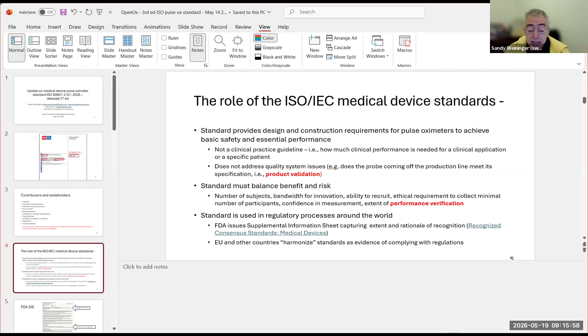And so I just want to make a few points here in the interest of time. This is an engineering, if you will, design specification standard. It is not a clinical practice guideline. So it does not tell you, the clinician, what level of performance or accuracy you need for a particular clinical application. Right? It's designed to verify that a product delivers the specified performance that's claimed in the labeling, and at least from an FDA perspective, that the manufacturer claims when they do their regulatory submission.